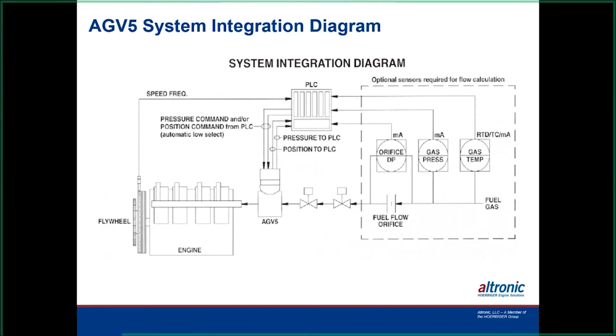Here's a little bit of layout on it. You run 24 volts to it, then you run a 4-20 to it to control it. It also has a 4-20 feed out that will tell you the positioning of the valve, and that's being utilized more and more as we get into these PLCs and other types of computer devices. It requires a speed input. Again, like I said earlier, we don't recommend tying this to another speed pickup. It should be a standalone pickup. This is actually controlling the speed of the engine. It has a little transducer in it that will also read header pressure internally.